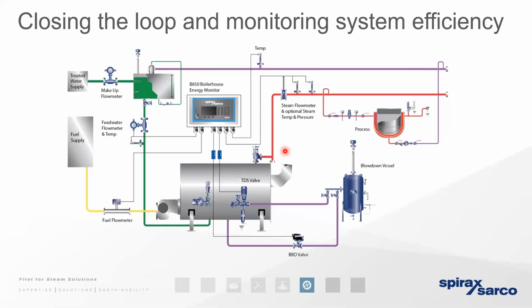And for the vast majority of cases, it will be down to the fact that we're simply not recovering as much condensate. Remember, if we're failing to recover that condensate, it could be for reasons of failed or cavitated condensate pumps, condensate being dumped to waste for fear of contamination, or failed steam traps or flash steam vents, both of which mean that we're reducing the amount of condensate that could be returned. If that were to happen, we'd need to replace that condensate with more water coming from the mains, and we need to bring that water up to temperature again. So we can make sense of all of that to identify the financial implication and where that inefficiency was being caused in the first place.